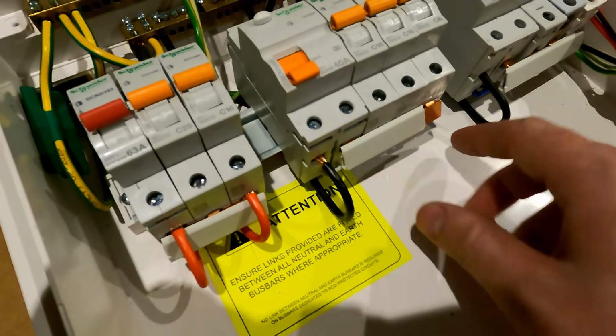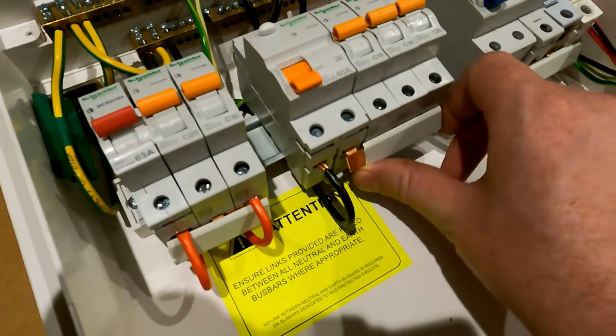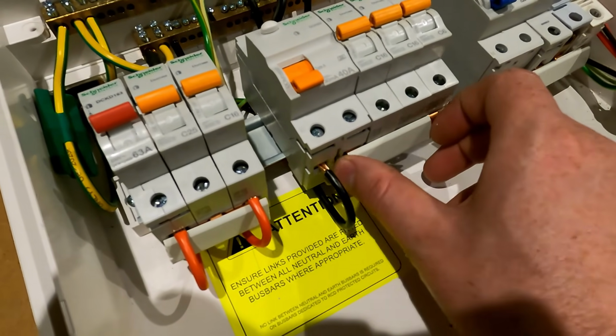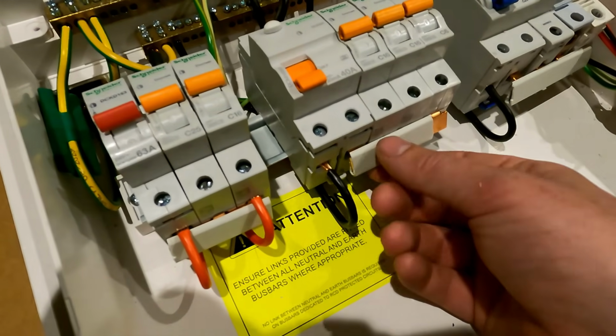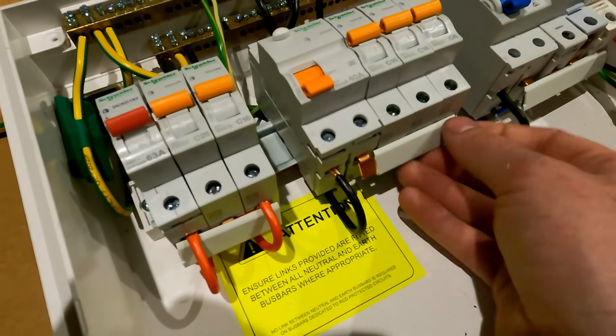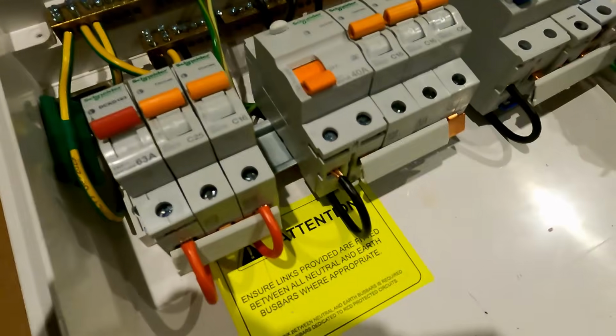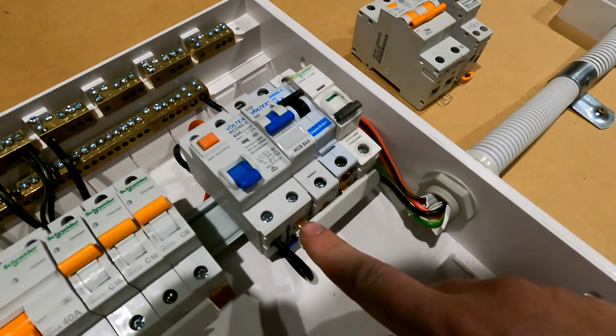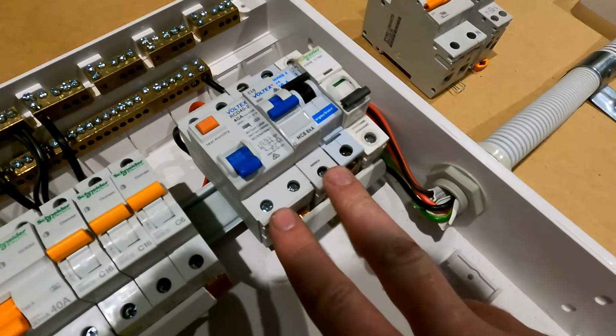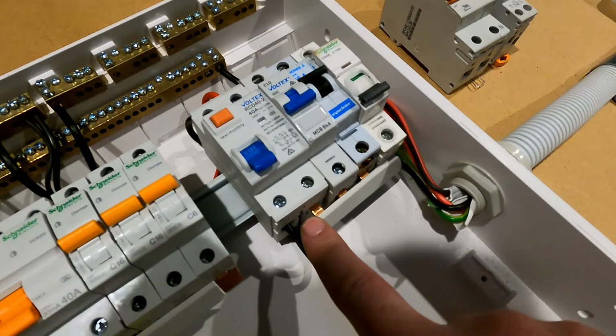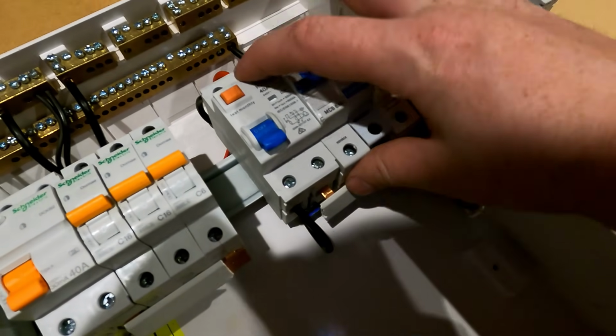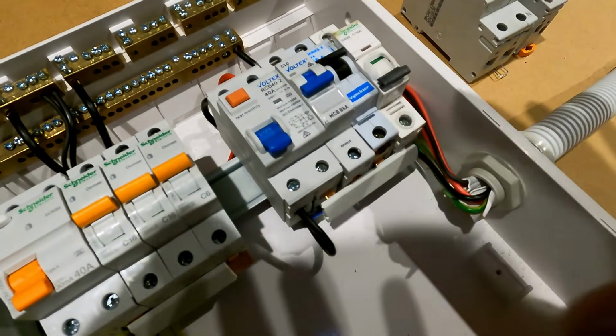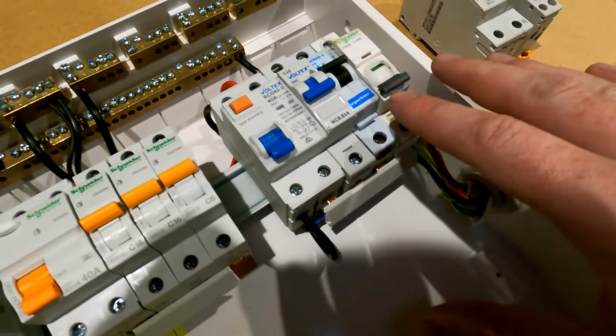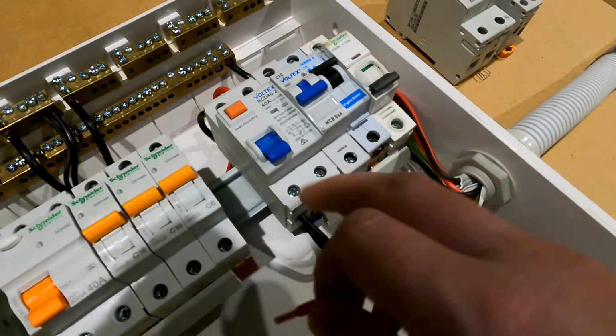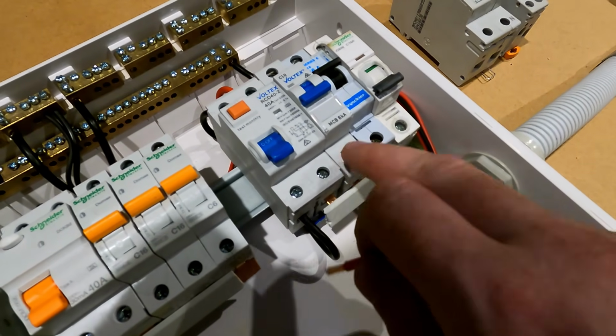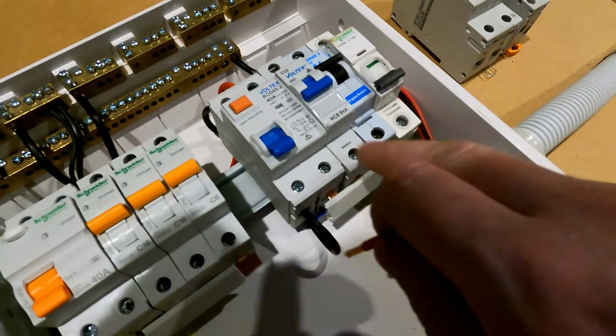The next thing on here is this phase bar, bus bar. If you have a look at this, the plastic shield or insulation on it has been cut too short. So what we'll have to do is cut a new one of these and put it on. You'll probably have to take the whole thing out and start again. And looking further down, sometimes you'll come across circuit breakers and RCDs that are different sizes, such as this Voltex brand. The phase bar actually sticks out way too far. And the other thing is, if you try and line them up, you're going to have a hard time putting the cover on because these aren't going to line up properly. So don't even try doing that. Throw a bit of 6mm between the load side of the RCD and the first circuit breaker and then run this bar across from there.